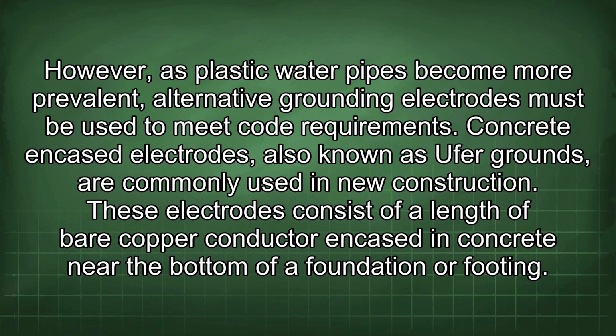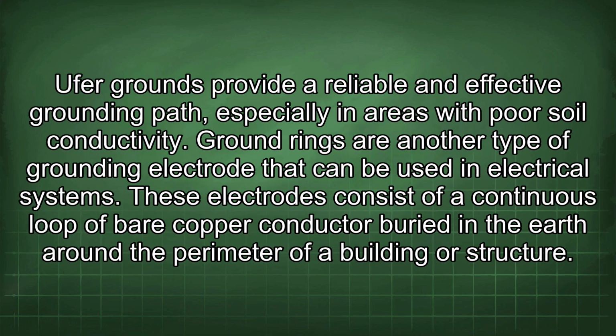Concrete encased electrodes, also known as UFER grounds, are commonly used in new construction. These electrodes consist of a length of bare copper conductor encased in concrete near the bottom of a foundation or footing. UFER grounds provide a reliable and effective grounding path, especially in areas with poor soil conductivity.